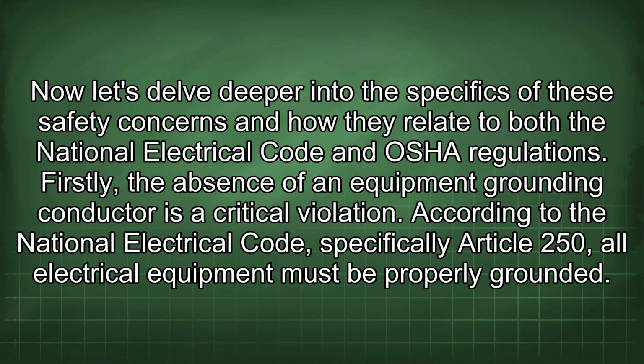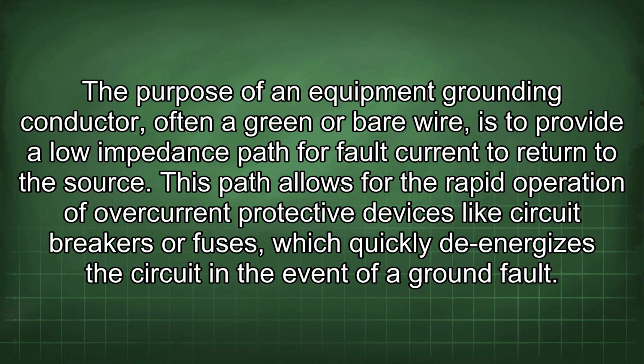Now let's delve deeper into the specifics of these safety concerns and how they relate to both the National Electrical Code and OSHA regulations. Firstly, the absence of an equipment grounding conductor is a critical violation. According to the National Electrical Code, specifically Article 250, all electrical equipment must be properly grounded. The purpose of an equipment grounding conductor, often a green or bare wire, is to provide a low impedance path for fault current to return to the source. This path allows for the rapid operation of overcurrent protective devices like circuit breakers or fuses, which quickly de-energizes the circuit in the event of a ground fault.